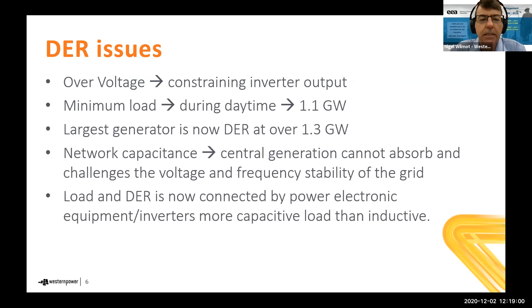change is a combination of a decreasing load level and increased voltages. Also, our load has changed from a lagging power factor of about 0.9 to 0.95, driven by motor loads and other inductive type loads, to everything, even your humble washing machine and refrigerators, now powered by a variable speed drive type device, which has power electronics, which runs at unity and at lightly loaded situations. So basically it looks like a capacitor to the grid. So peak load no longer is poor power factor. At our peak loads on individual distribution transformers, we're usually seeing unity power factor at peak, which completely changes the characteristics of things.